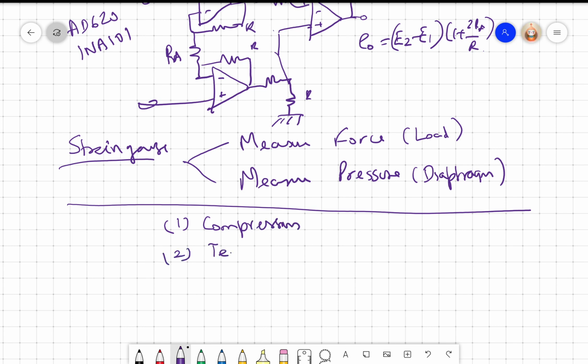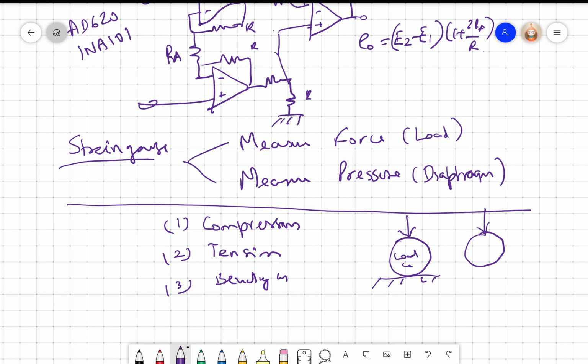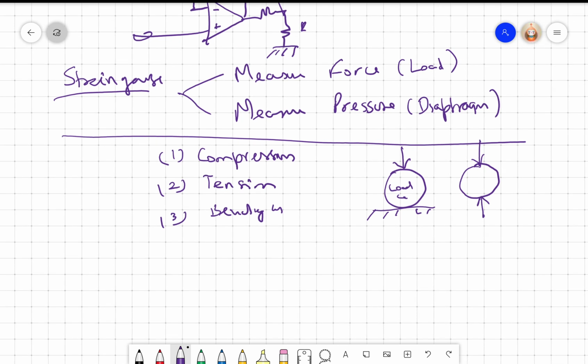Second is the tension type load cell. Three is the bending type load cell. Compression load cell: if this is the load cell, you compress it, put the force down, so the structure gets compressed. Or you can also use differential compression. You put one on top, one at the bottom. Then also you get compression. Of course, this is compression.